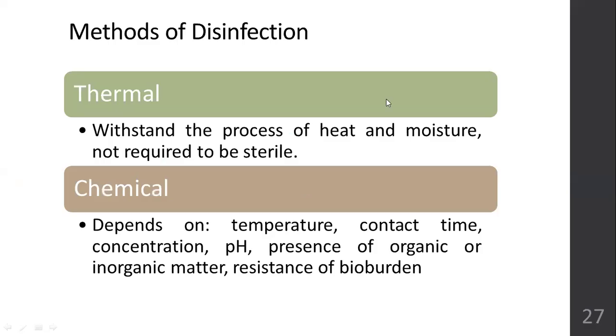Then methods of disinfection: you have thermal methods and chemical methods. Thermal methods can be used for things that can withstand heat and moisture and do not need to be sterile, using hot water or a heated environment. Chemical disinfection depends on temperature, contact time, concentration of the detergent or disinfectant used, pH, presence of inorganic and organic matter, and resistant bioburden, that is the resistant bacteria which are there. So based on all this information, a chemical method is chosen.